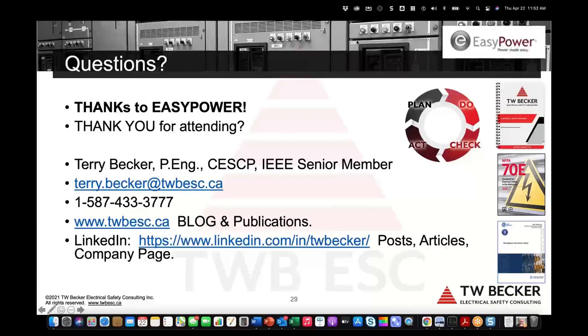Here's a question about PPE. Any idea about the weight of the full suit and face shield that's suitable for 140 calorie exposure? So when you look at these hoods, this is an example of a 75 cal hood, and I'm assuming everybody can see my camera still on. This is very lightweight. If I'm holding this up, you can see it's very thin. The layering technology for all of the arc flash suit vendors has evolved. So the total ounce weight of the multiple layers of fabric is very light now. The total weight of this hood or the jacket or the bib overalls is unbelievably lightweight now.